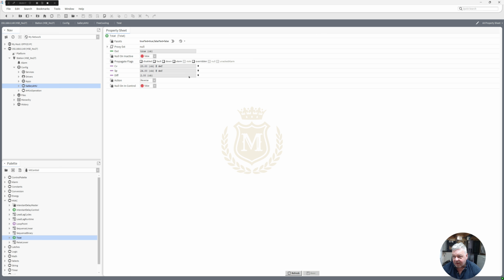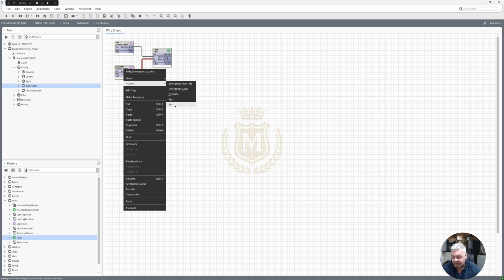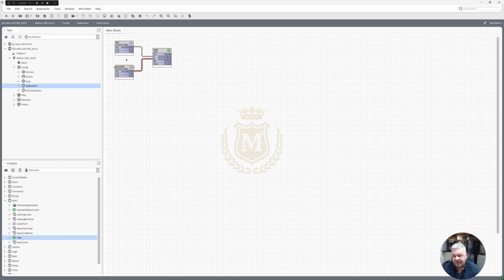So if we change it, say we didn't go for 1 degree and we went for 2 degrees either side, and we'll set that down to 20, false. Actions set to 24, it's still false. Last time it was true. Set that to 25. It's now true. So we've now got a 2 degree differential, and we can make a set point for that so the client can adjust what differential they want.